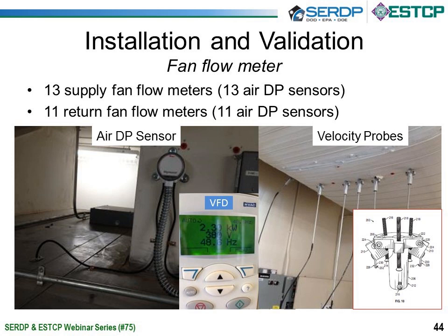There are fingers on this device that are hanging down in this picture, but they go up through the hole. When you insert the probe through the middle hole, it forces the fingers out, which hold the mounts inside there, and then we have some set screws for the probe to adjust its penetration into the duct, and we have some 3 screws that allow us to align this so it's perpendicular with the flow.